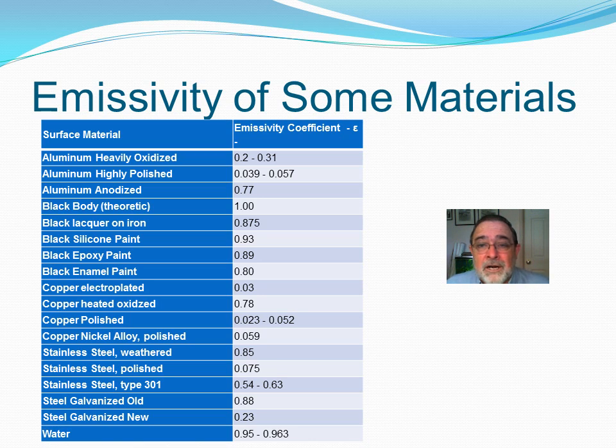Because it's going to oxidize, and when it oxidizes, it's going to lose more of its heat, but it's also going to generate more heat. You become a high resistant joint. Okay, so the emissivity changes over temperature range and with oxidation, but the number rises in the copper from about 5% or 0.05 to 0.78 or 78% emissivity.